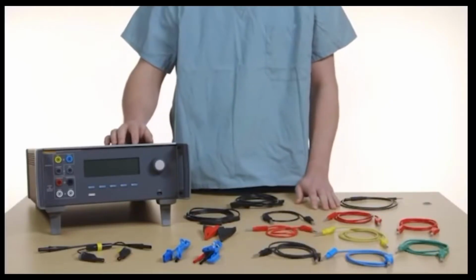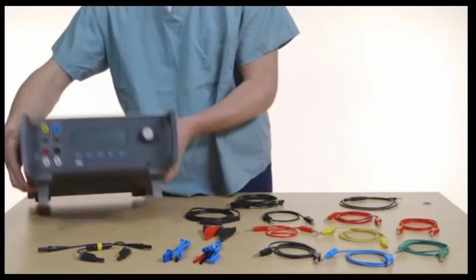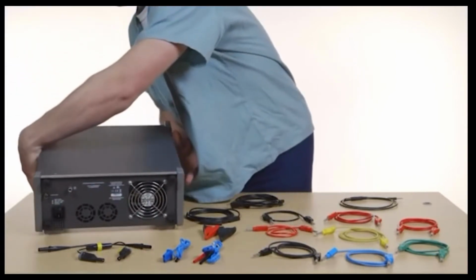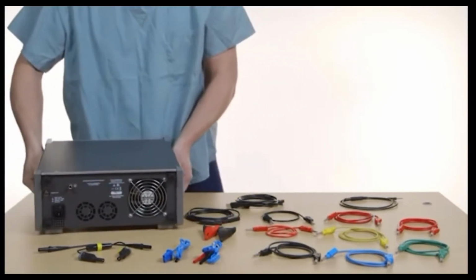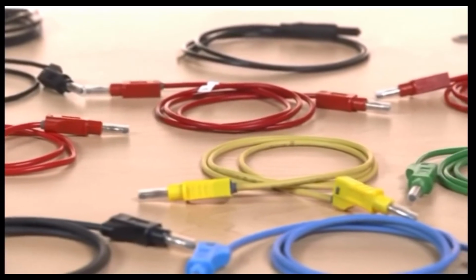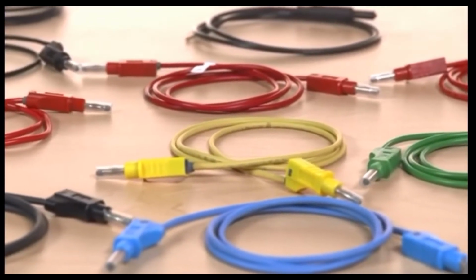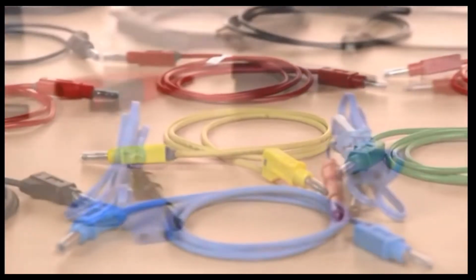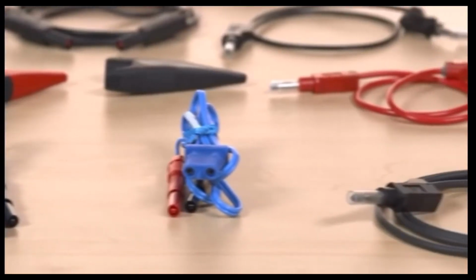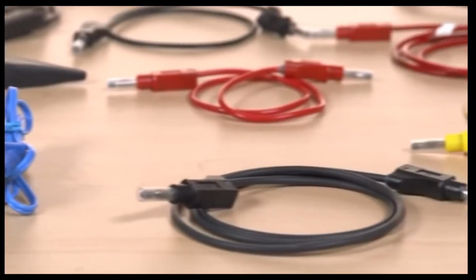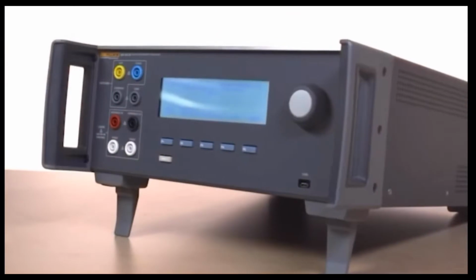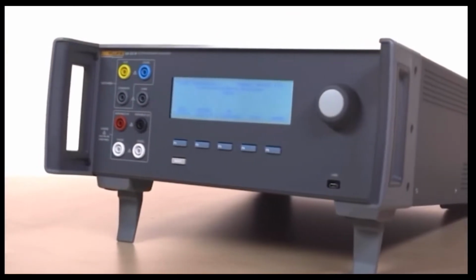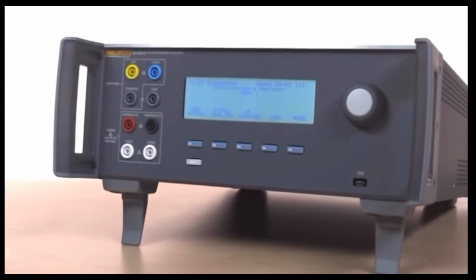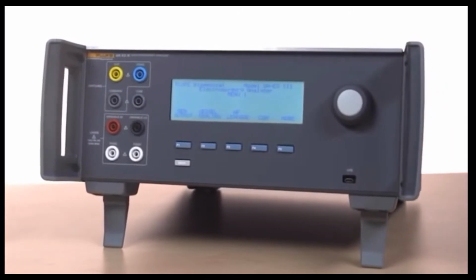When you pick up the QA-ES3, you'll quickly discover it's lighter than the previous version, 5.5 pounds lighter. Everything you need to test all critical functions of today's high-power electrosurgical units is either integrated into the design or included with the unit. There's no need for extra cables, leads, or switch boxes to test precision power, current, frequency, crest factor, and load resistance ranges.